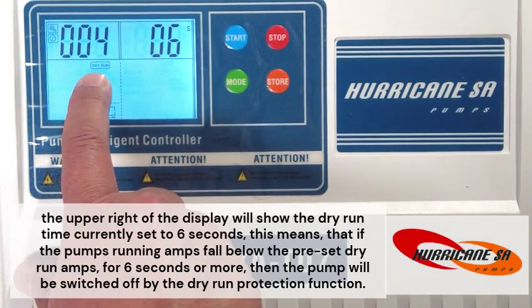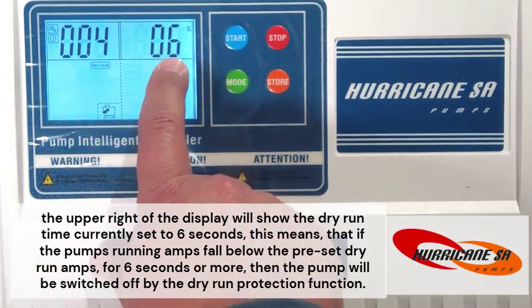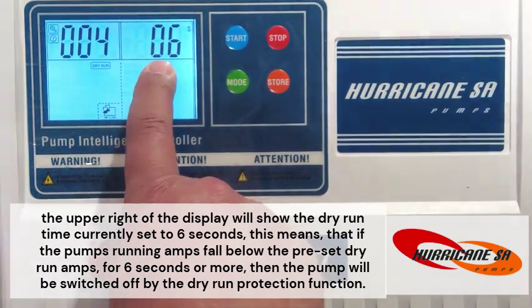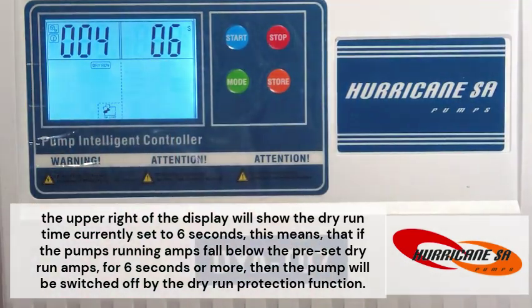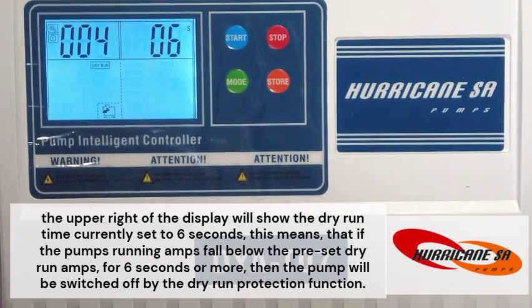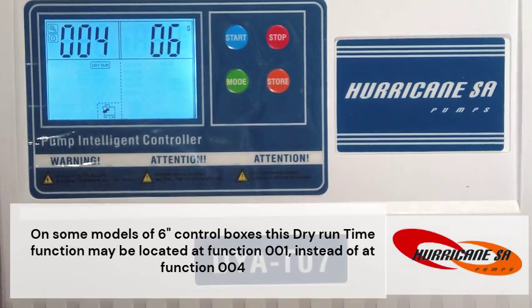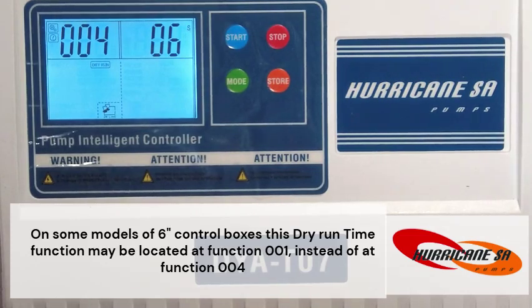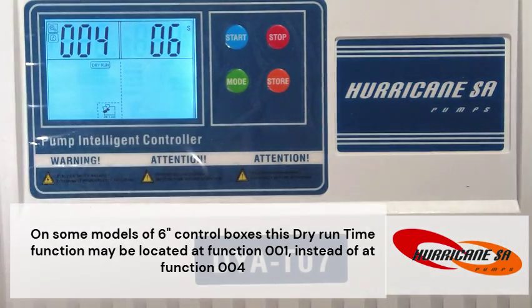The upper right of the display will show the dry run time currently set to 6 seconds. This means that if the pump's running amps fall below the preset dry run amps for 6 seconds or more, then the pump will be switched off by the dry run protection function. On some models of 6-inch control boxes, this dry runtime function may be located at function 001 instead of at function 004.